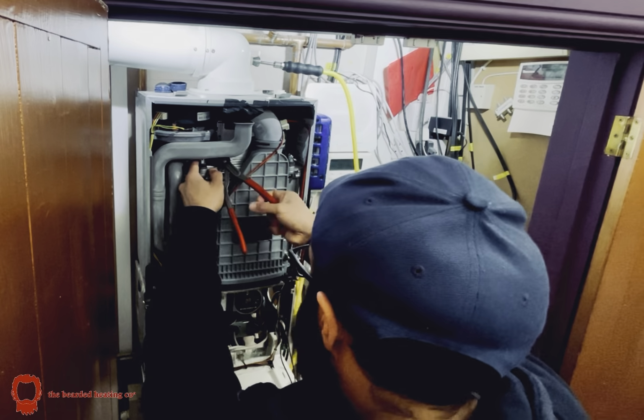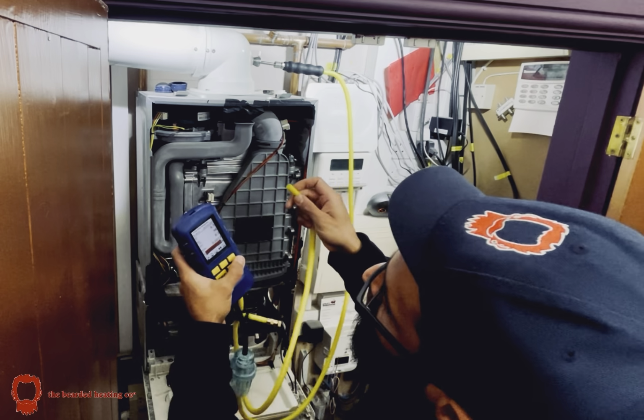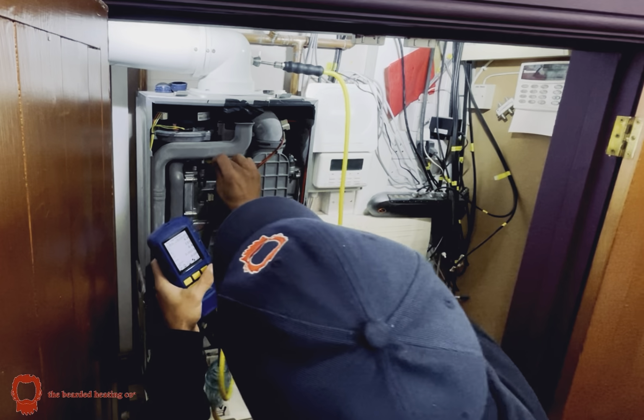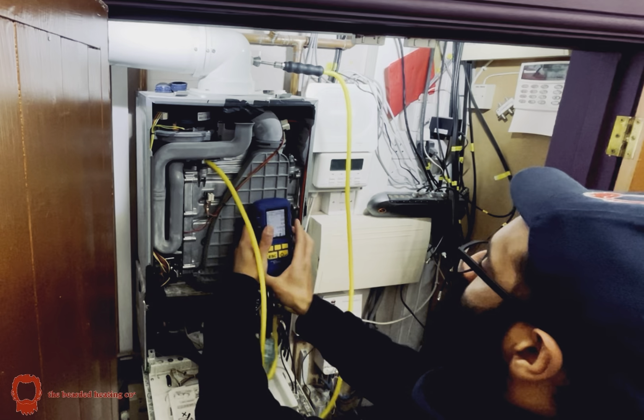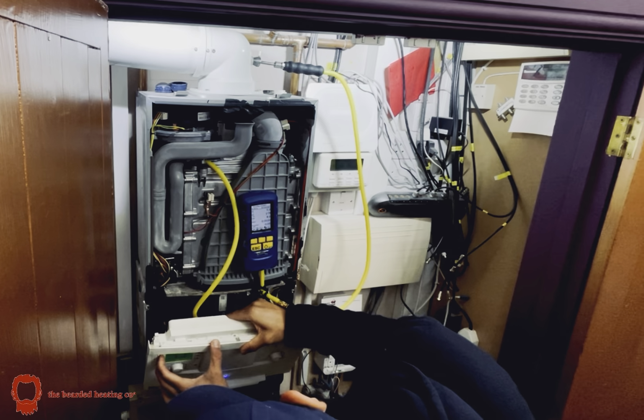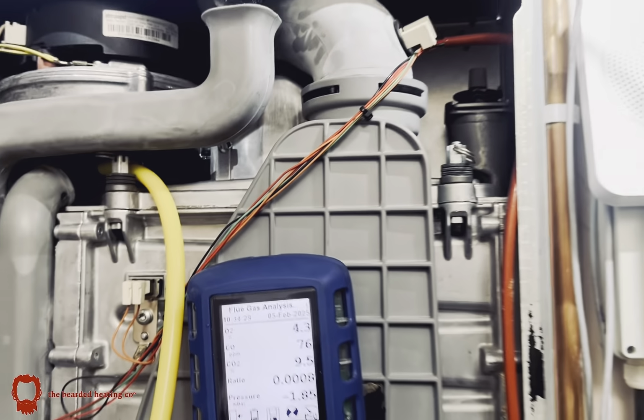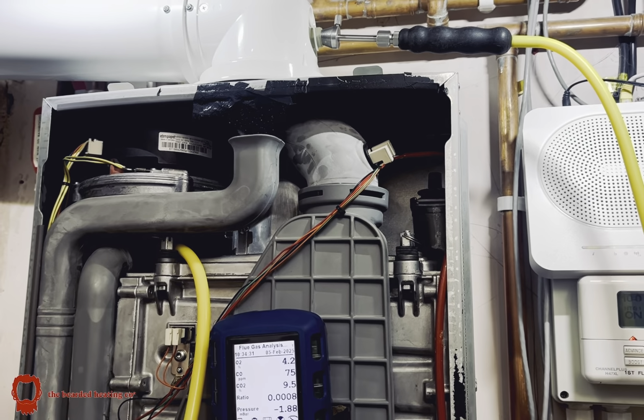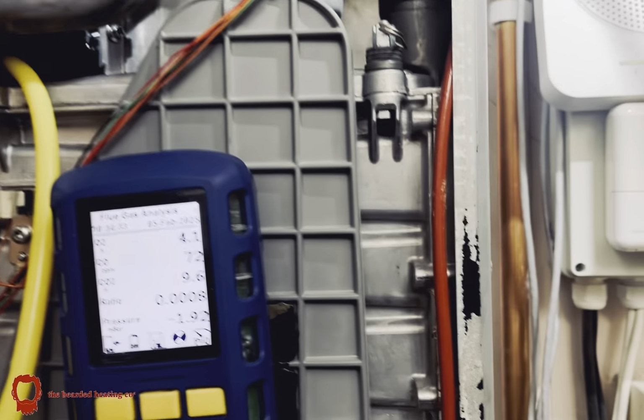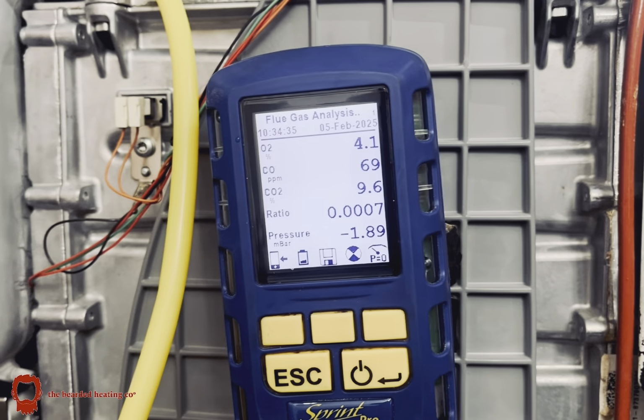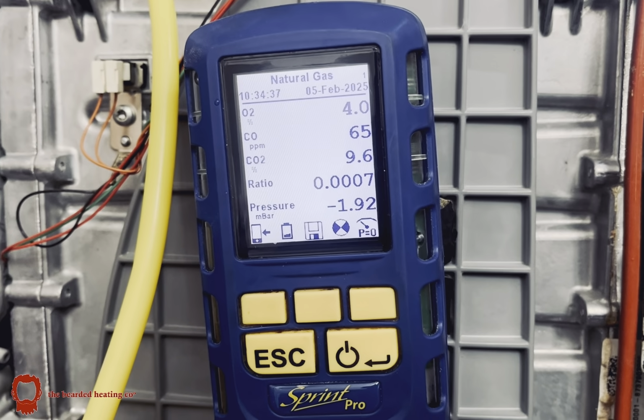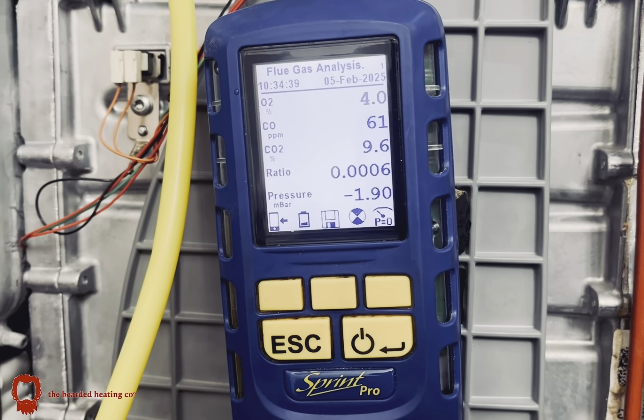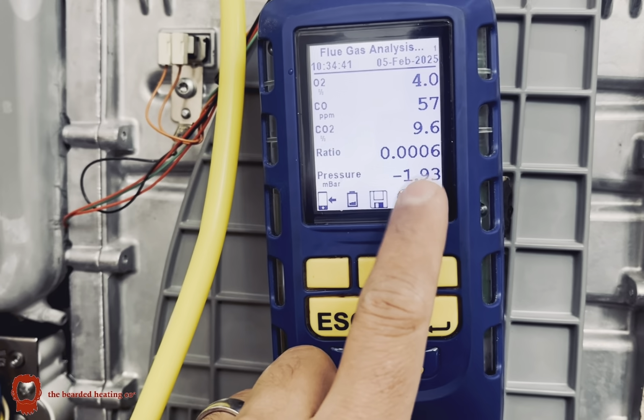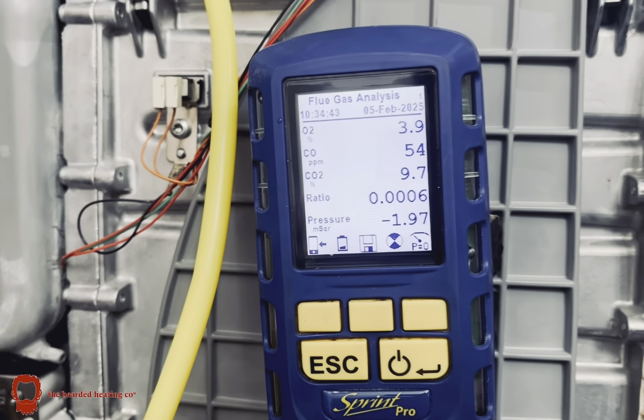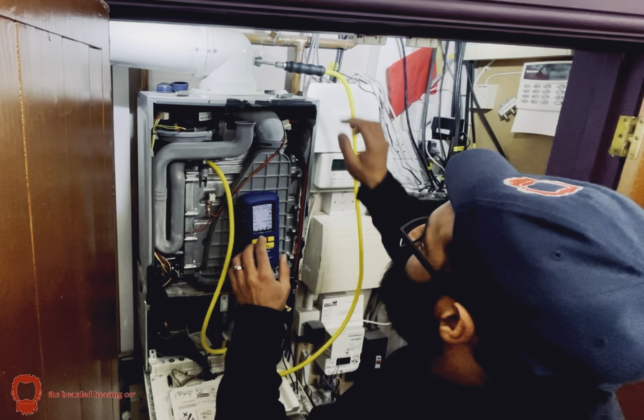Right now I'm showing you how I carried out a negative fan pressure test by connecting my FGA to the test point on the fan. Put the boiler into high fire, and you can see my negative fan pressure is less than -2 millibars, and it should be a minimum of -3.2 on this particular model of boiler.